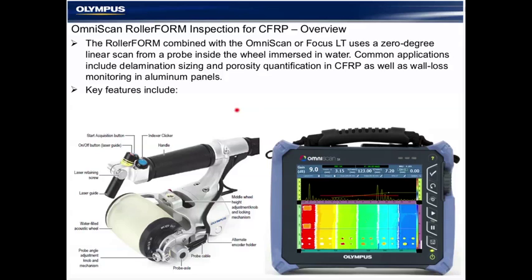Today, we're going to be learning about the latest exciting new product from Olympus that's a perfect companion for the OmniScan SX and MX2, the RollerFORM wheel probe. The RollerFORM wheel probe is designed to provide an immersion type inspection on CFRP, that's carbon fiber reinforced panels, aluminum panels, and similar components typically associated with the aerospace industries.